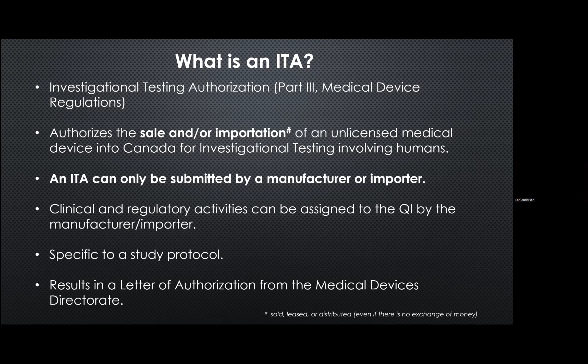The ITA is specific to a study protocol. So if you get authorization from Health Canada for use of a device that's unlicensed, and you're going to be using it in one of your studies, it is only specific to that protocol. You can't be using that device in numerous different protocols because you have an ITA authorization. It has to be specific to that one protocol. And what you get is actually called a letter of authorization from the Medical Devices Directorate that allows for that sale and or importation of the device.